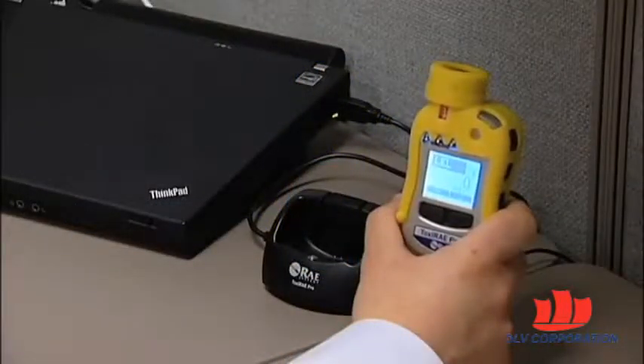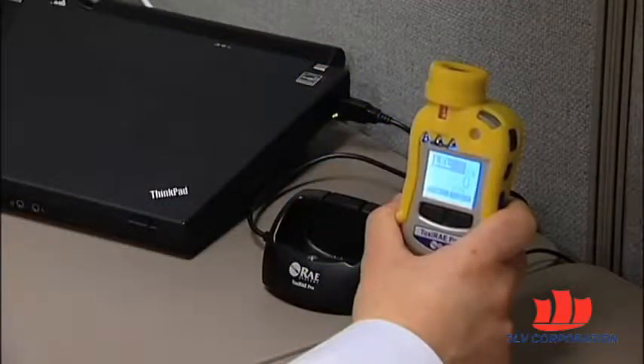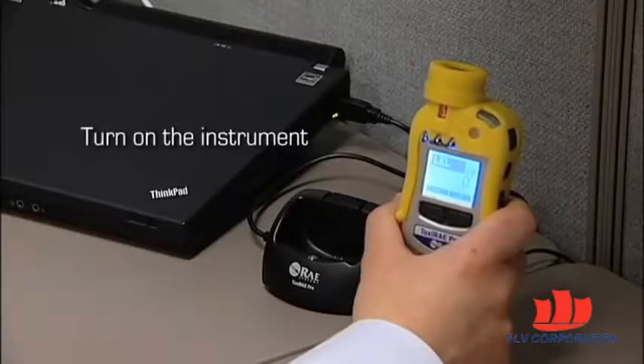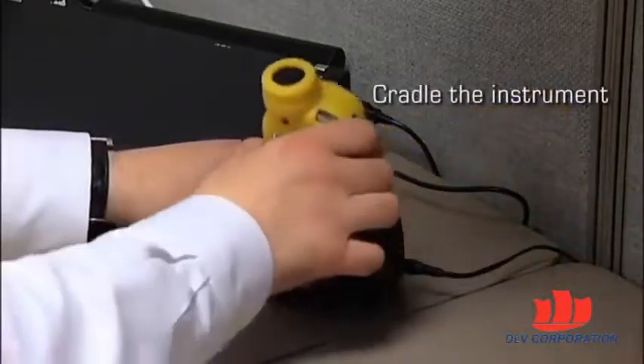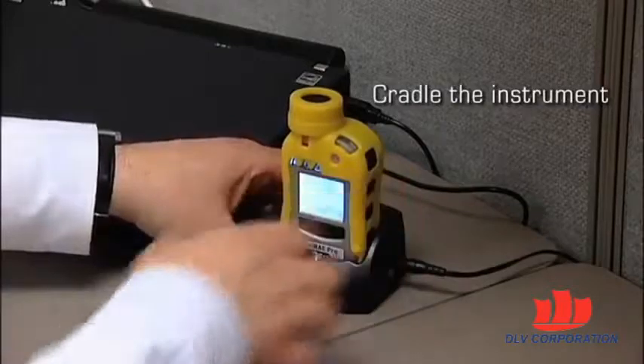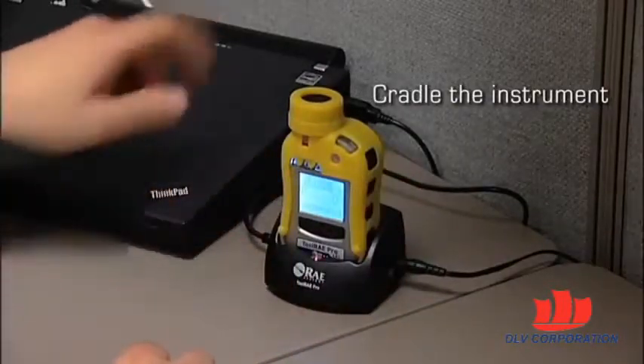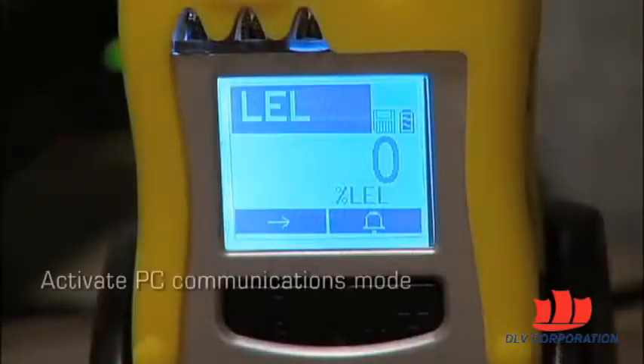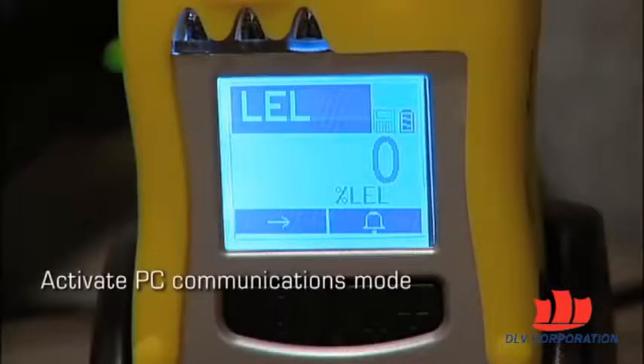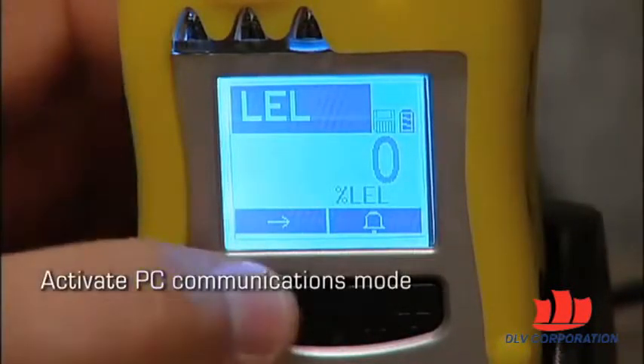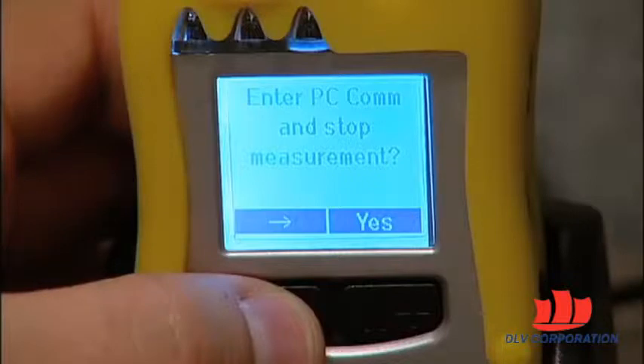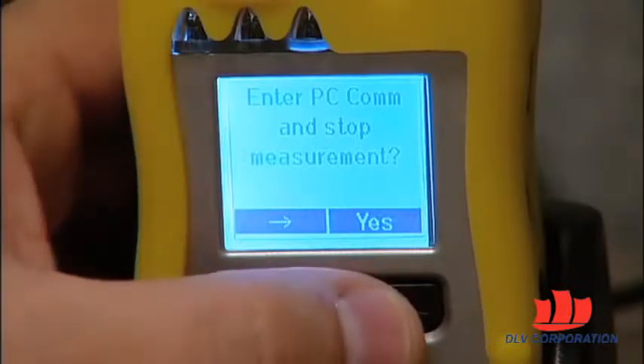To download data from your ToxiRAE Pro to the PC, turn on your ToxiRAE Pro and make sure it boots up fully to see the measurement screen. Insert your ToxiRAE Pro into the charging and PC communications cradle and make sure the cradle is connected to the computer. The next step is to put your ToxiRAE Pro into PC communication mode. To do so, press the mode button repeatedly until you reach the screen that says 'Enter PC Com and Stop Measurement', then press yes.